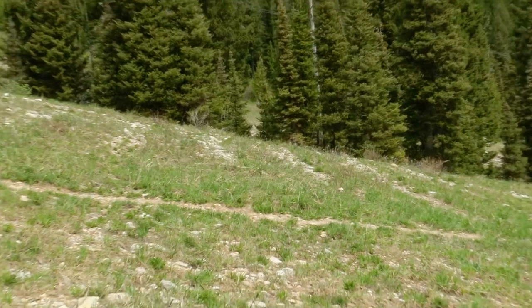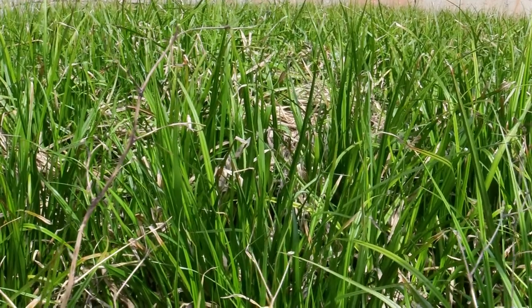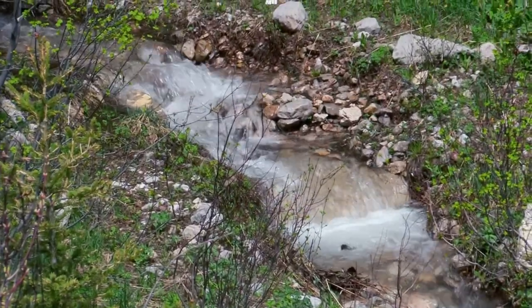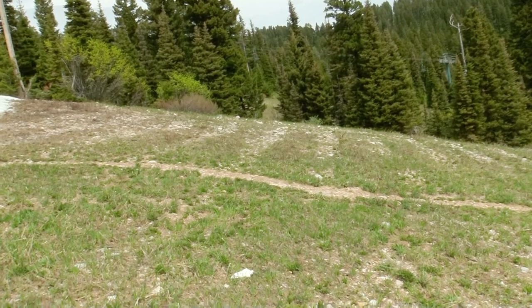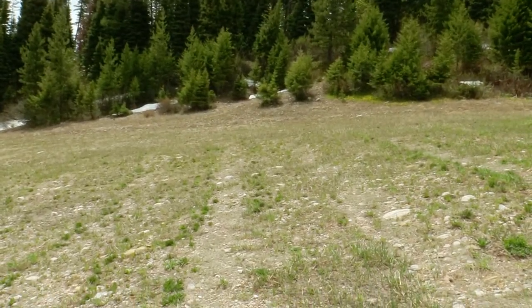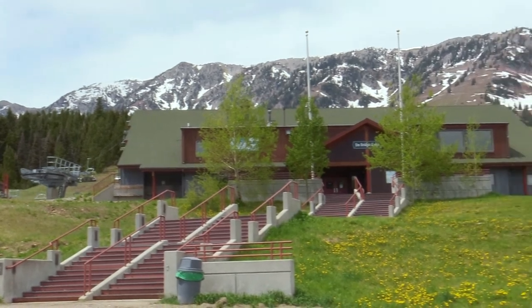The idea for the wetland was to remove enough nutrients that it's safe to put into the drain field. The issue is nitrogen — there's no phosphorus limit because it's a soil discharge system and phosphorus binds to soil well anyway. Nitrogen, however, goes right through into streams. We can hear a stream over there. It causes eutrophication because some streams are really nitrogen-limited, and suddenly nitrogen shows up and it's lunchtime. We also take advantage of natural bacteria in the interstitial areas for final treatment. For an individual home the flow rate is so small you don't need the wetland pre-treatment step.